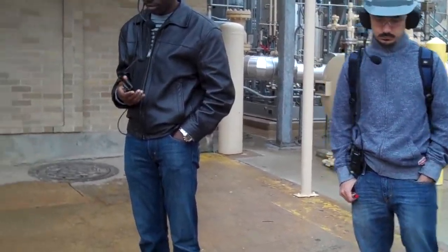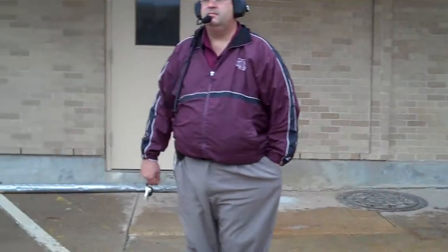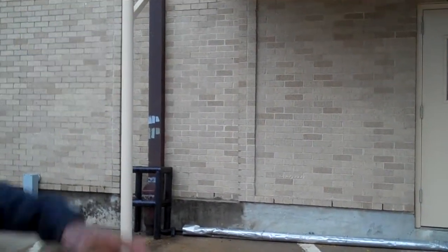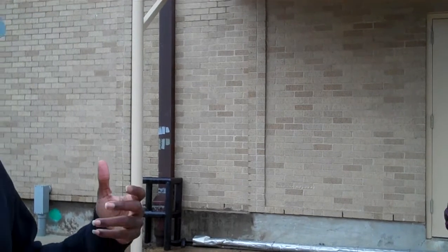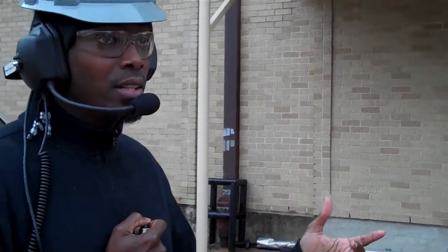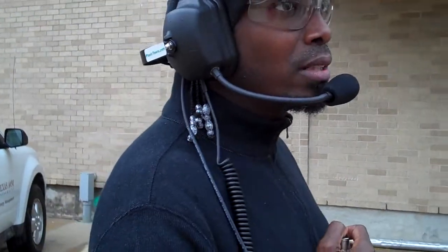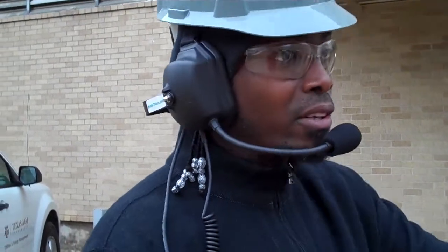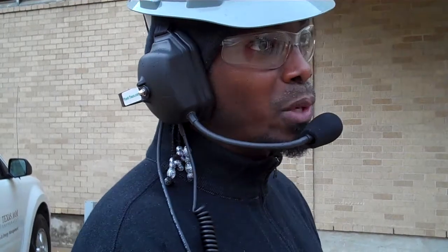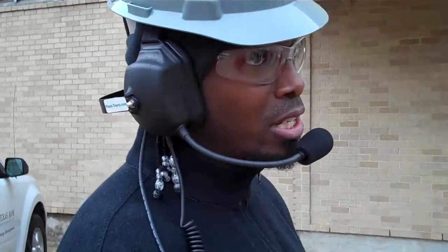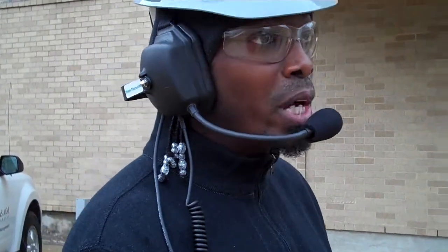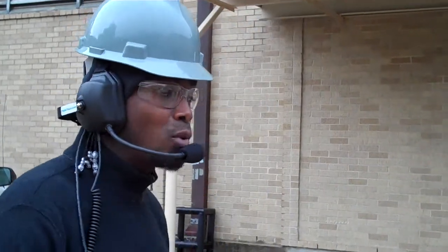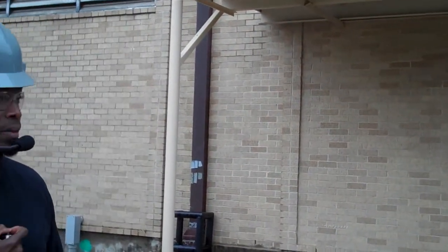That's right. To be able to function properly with the particular mapping they have in place for this particular gas turbine. Now, in commissioning, there had to be some fine-tuning several times to get it right. So it does matter what kind of gas we're getting in here, and we do make adjustments. We actually heat it up as well, and then do some conditioning as well to make sure that we have what we need to get it to run right.